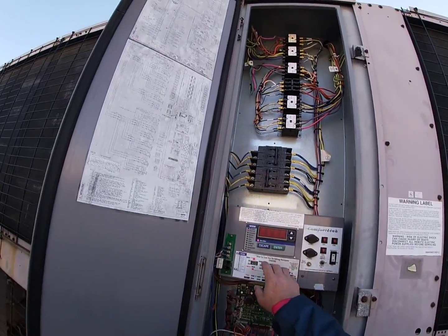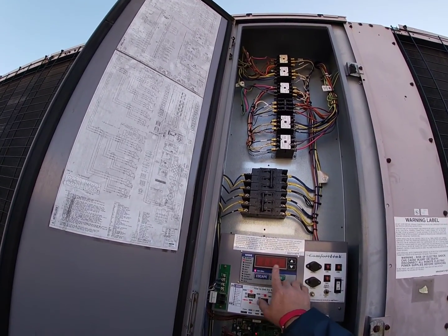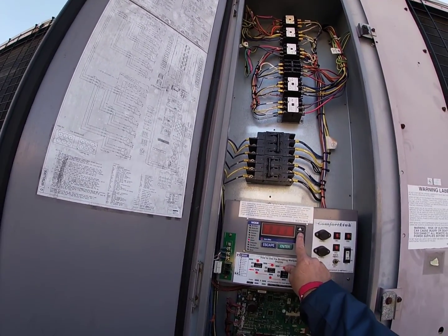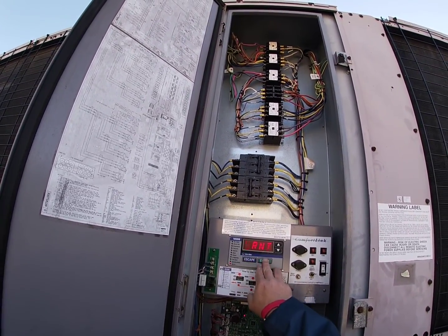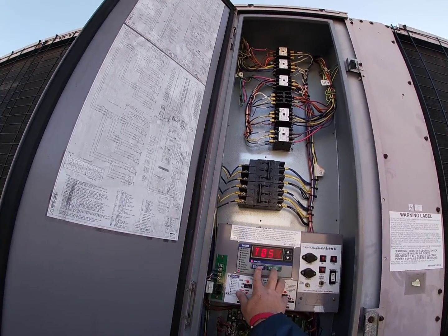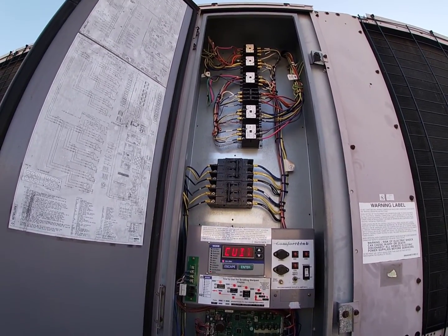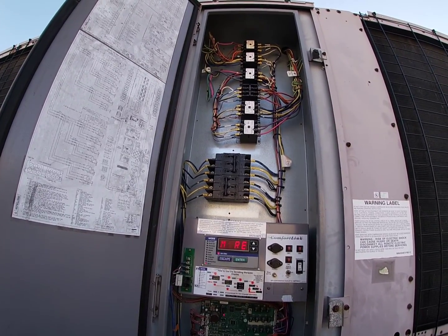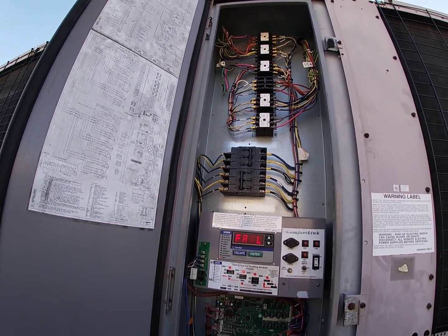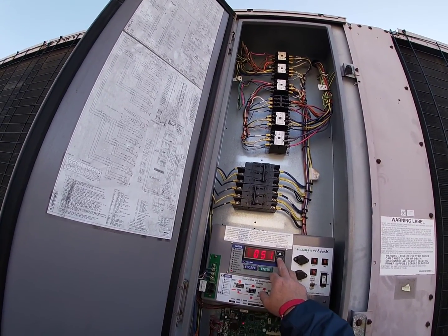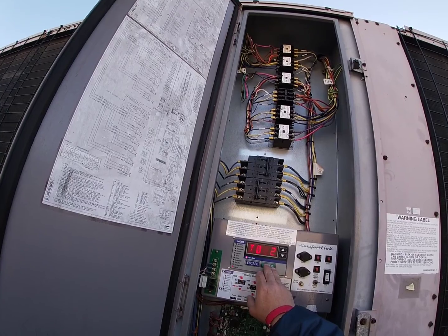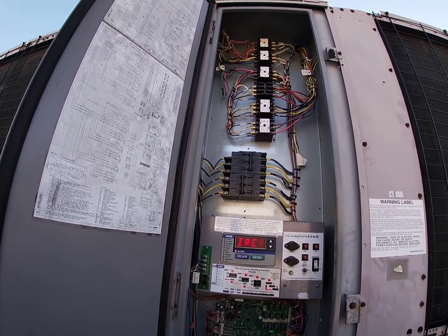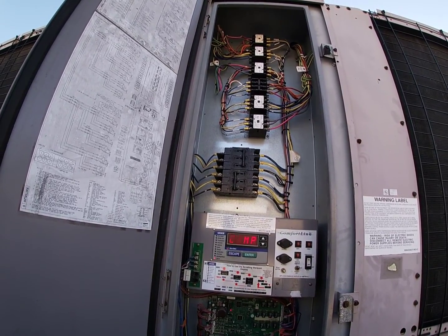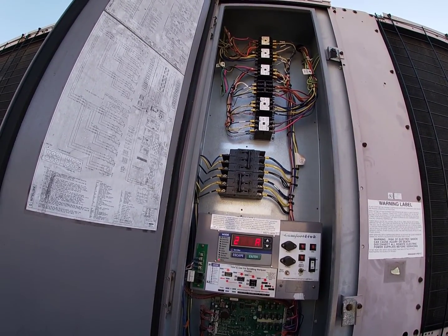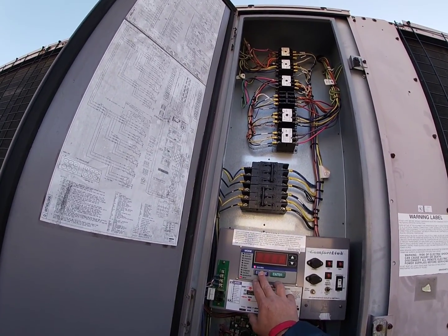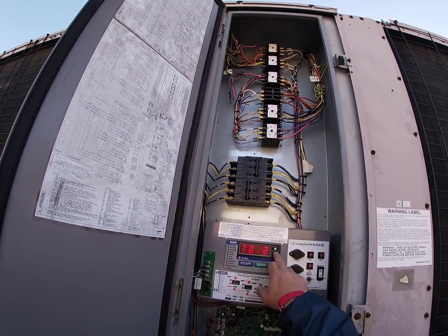Kind of show you guys what's going on with this one here, but you got an alarm status here. Let's go to alarms. So right now your current, we have a T051, which is a compressor 1 failure, circuit A, compressor 1 failure, and then you have two alarms on here, circuit A, compressor 2 failure as well. So I didn't see any other ones yet, just those two here.